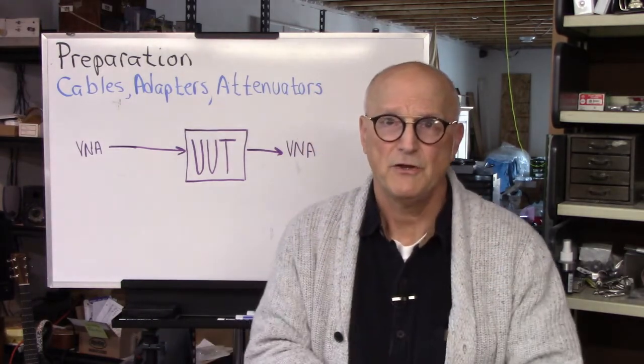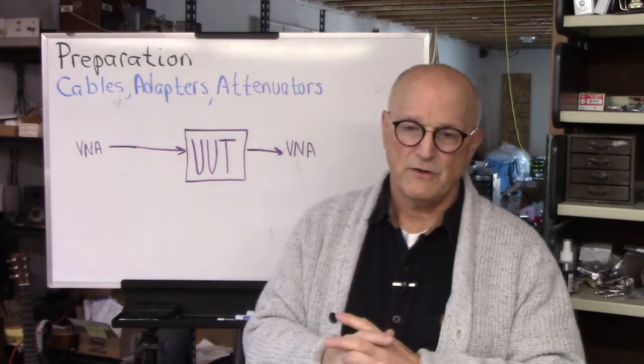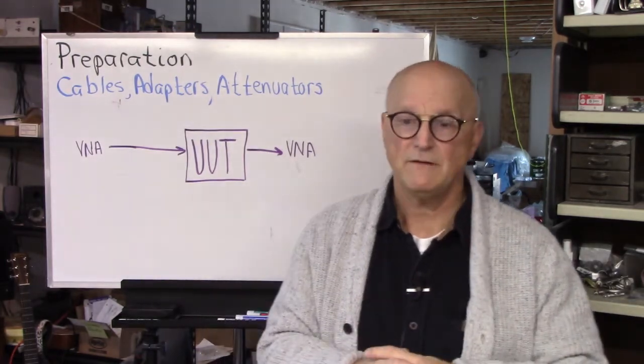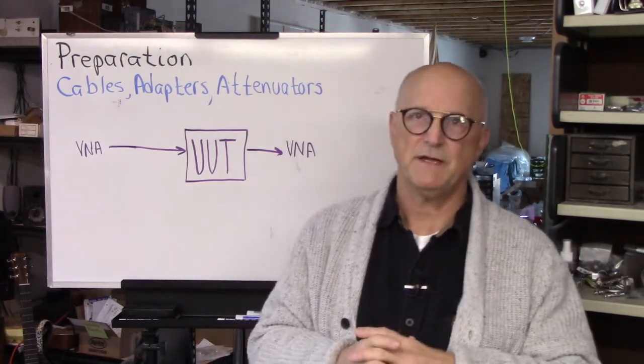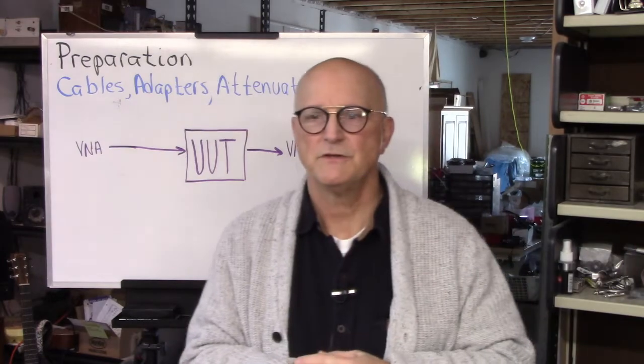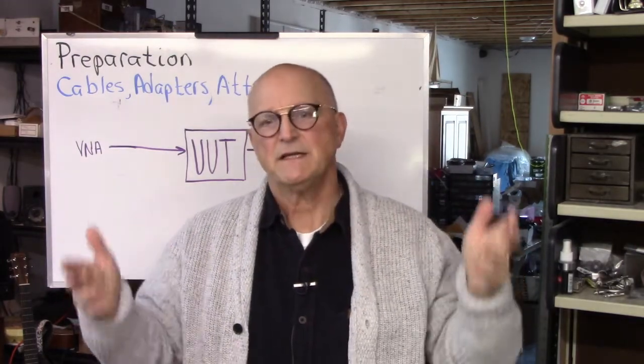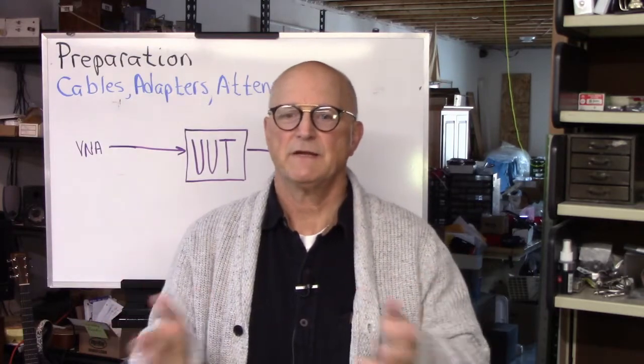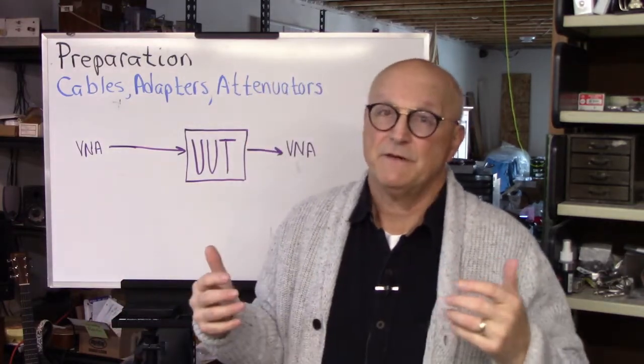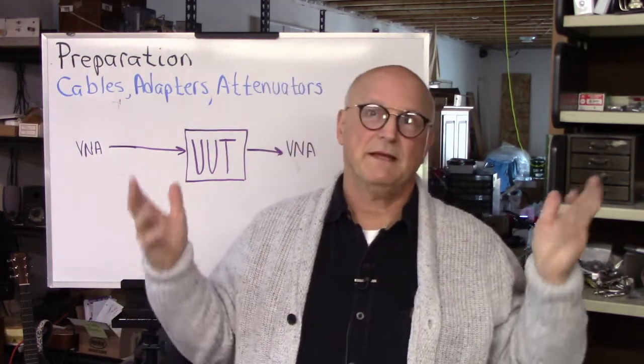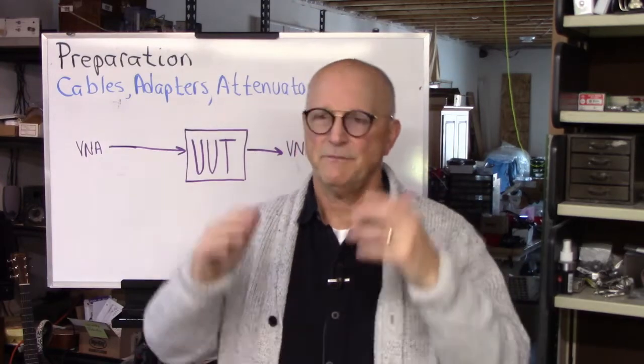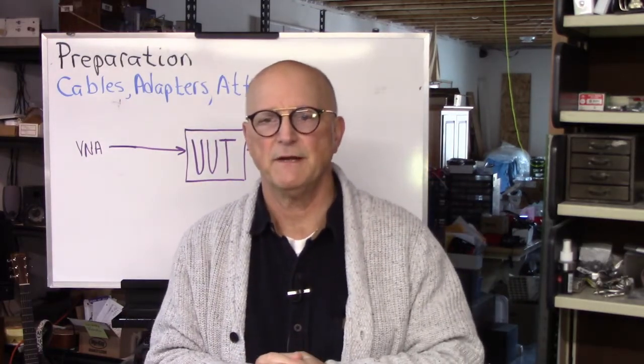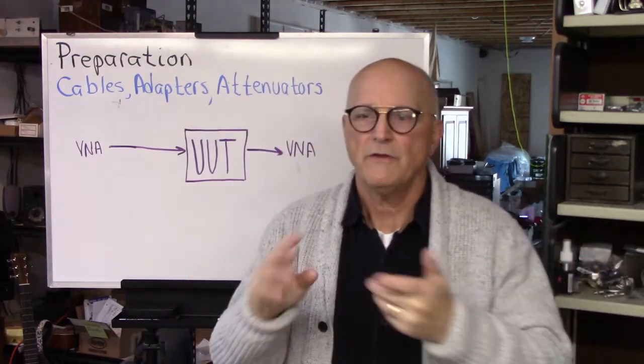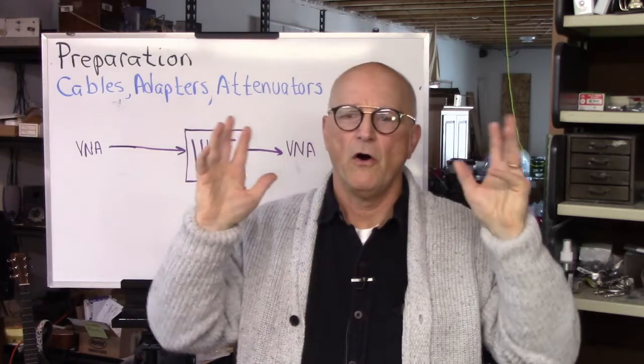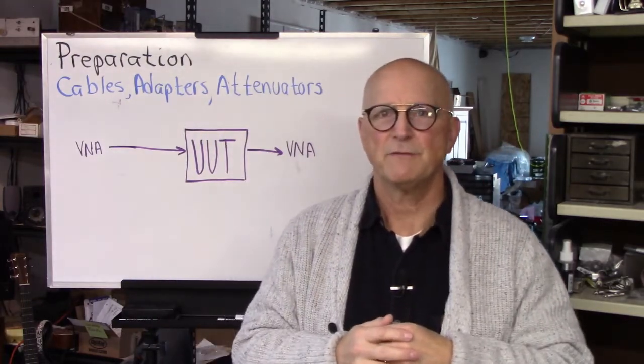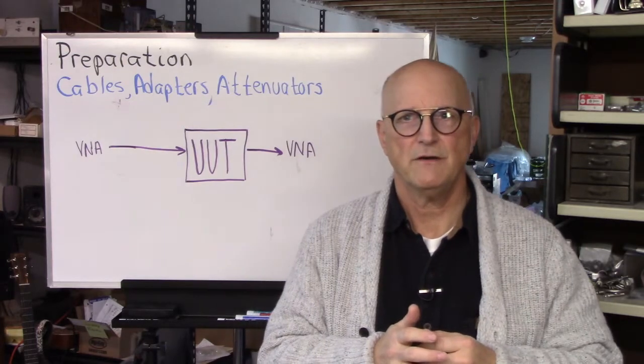But for you and your particular VNA, the only way you're going to know what your particular VNA will do well is to experiment, play with it, see how it does things and what it will let you do. And as before, I emphasize again, every cable and every adapter does make a difference in the measurement. As to whether that difference is enough to be concerned with, that's entirely up to you and what you're trying to do and the precision and the accuracy of the measurement that you're interested in. So, you gather all the cables and attenuators and adapters and all of that stuff that you need for both calibration and measurement in preparation for doing your calibration and measurement.